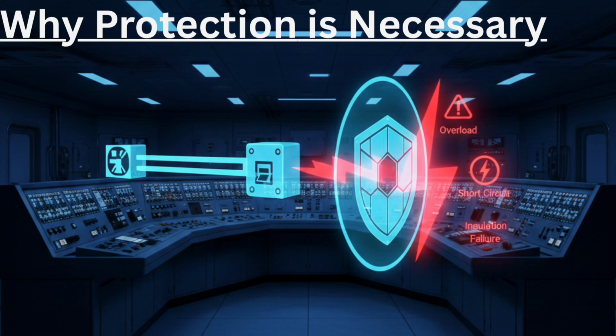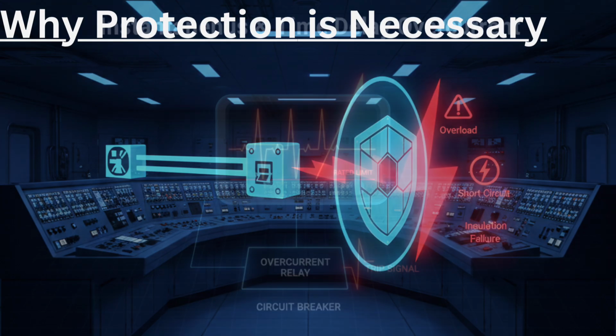Protection relays detect abnormal conditions very quickly, much faster than any human operator. They automatically send trip signals to circuit breakers to isolate the faulty part. Protection systems prevent equipment damage, electrical fire, generator failure, complete blackout. So we can say, protection relays are like security guards of the electrical system.